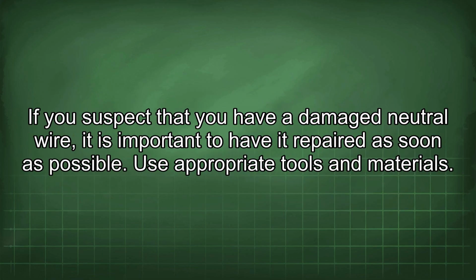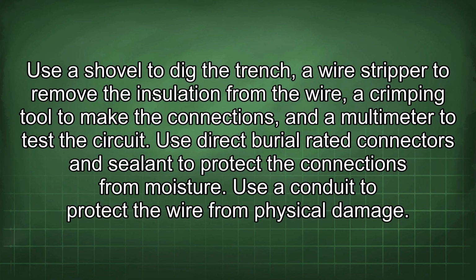If you suspect that you have a damaged neutral wire, it is important to have it repaired as soon as possible. Use appropriate tools and materials. Use a shovel to dig the trench, a wire stripper to remove the insulation from the wire, a crimping tool to make the connections, and a multimeter to test the circuit. Use direct burial-rated connectors and sealant to protect the connections from moisture. Use a conduit to protect the wire from physical damage.